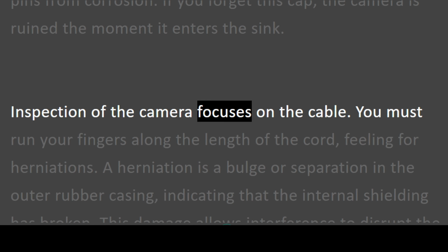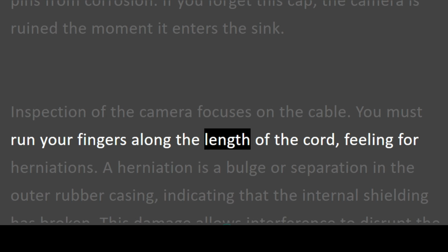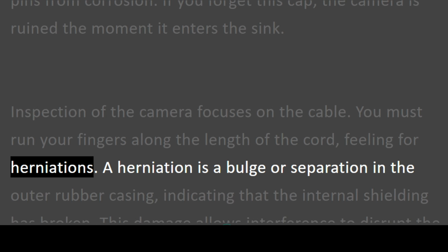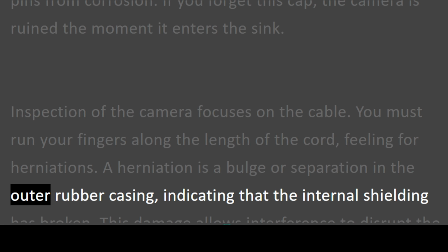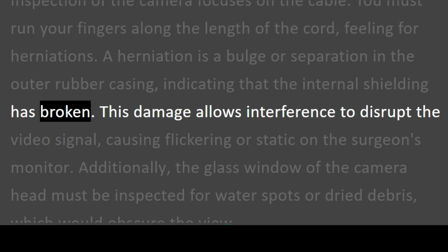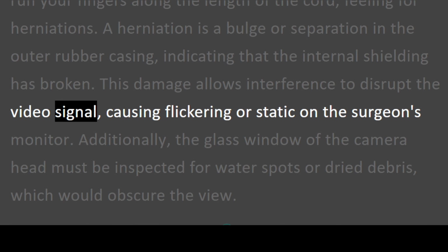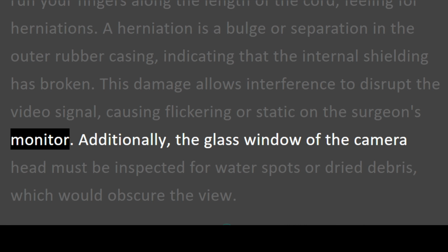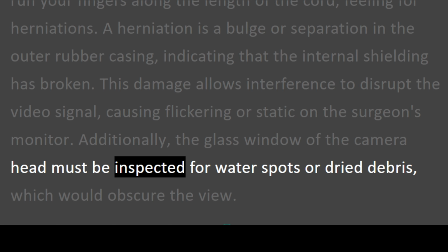Inspection of the camera focuses on the cable. You must run your fingers along the length of the cord, feeling for herniations. A herniation is a bulge or separation in the outer rubber casing, indicating that the internal shielding has broken. This damage allows interference to disrupt the video signal, causing flickering or static on the surgeon's monitor. Additionally, the glass window of the camera head must be inspected for water spots or dried debris, which would obscure the view.